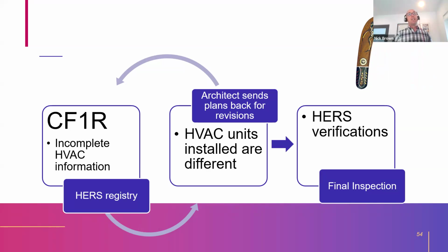Much better off having that HVAC system specified at the time you're submitting for permit, or have the HVAC sub follow what's on the compliance form. That way the HERS verifications go smoothly, as does the final inspection. For this reason, we now offer HVAC load calcs as part of our services, optional, but that way we do a load calc of the design ahead of time, find out, for instance, it's a 4-ton system for the first floor and a 2-ton for the second floor. We put that in our compliance model from the start, and that's what's installed.